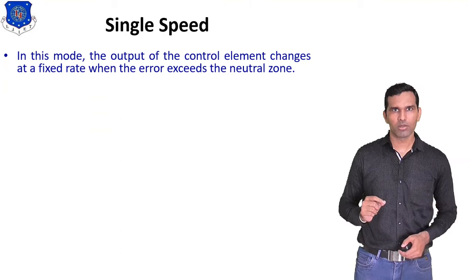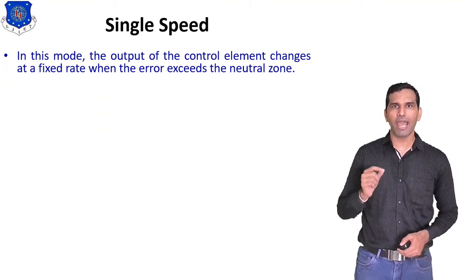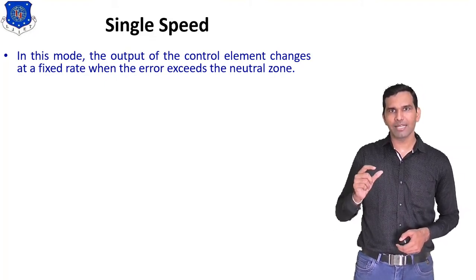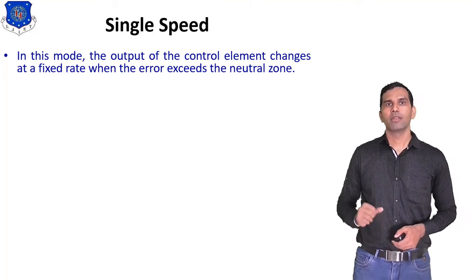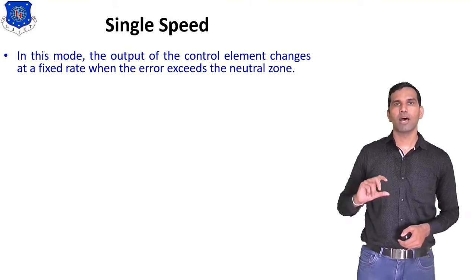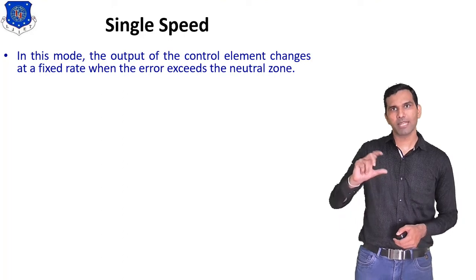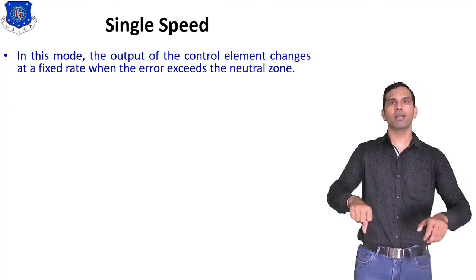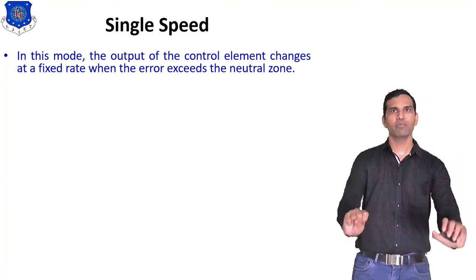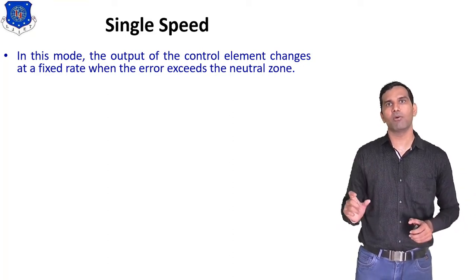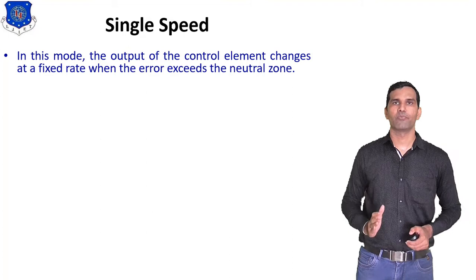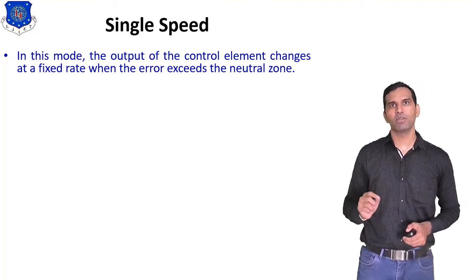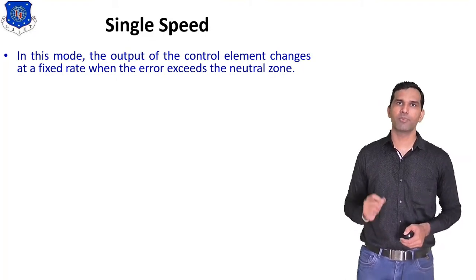In single speed control mode, the output of the control element changes at a fixed rate when the error exceeds the neutral zone. That means the output changes, but its changing speed remains fixed — like driving a vehicle at a constant speed of 60 km/h.